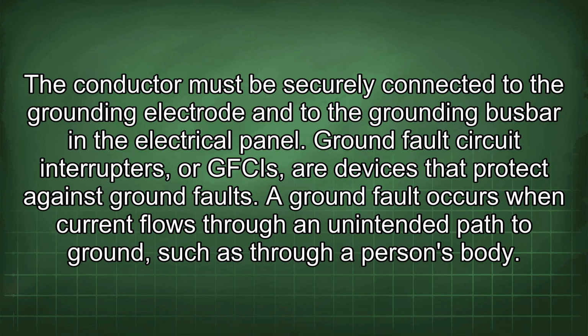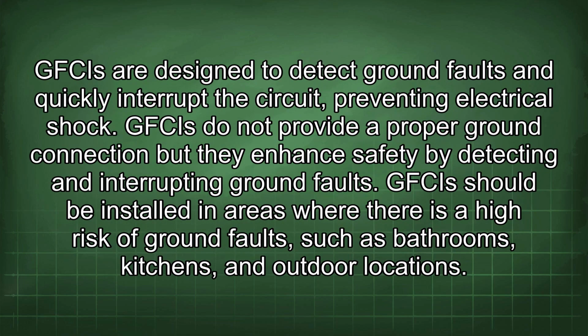Ground fault circuit interrupters, or GFCIs, are devices that protect against ground faults. A ground fault occurs when current flows through an unintended path to ground, such as through a person's body. GFCIs are designed to detect ground faults and quickly interrupt the circuit, preventing electrical shock. GFCIs do not provide a proper ground connection, but they enhance safety by detecting and interrupting ground faults.